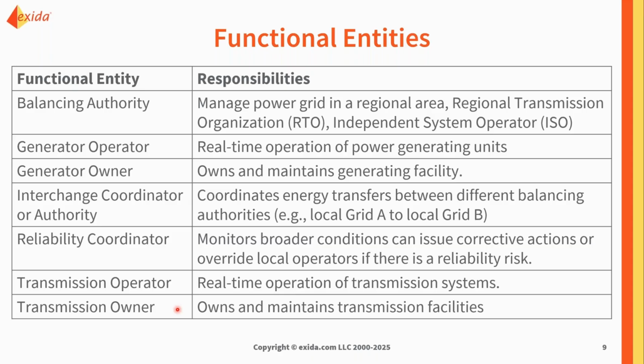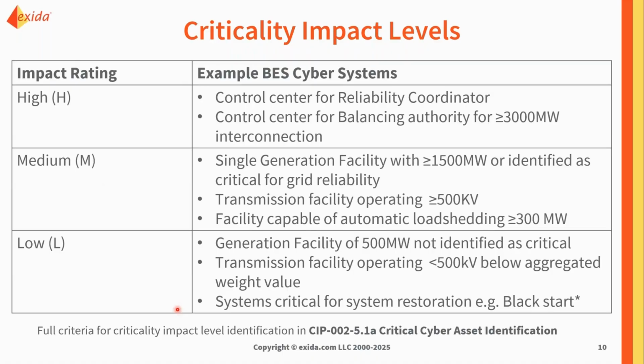The reason it's important to break this down into functional entities is that NERC CIP requirements are determined to be applicable or not based on the impact rating of a site, and the criteria for that rating are specifically defined for each functional entity. The full criteria and process for the impact level assessment are in part 2 of the CIP standards, and it's all about identifying critical cyber assets, which sites are critical, and which systems for those sites are critical. For anyone who falls under the NERC CIP standard, this is the place to start—you have to understand your impact level.